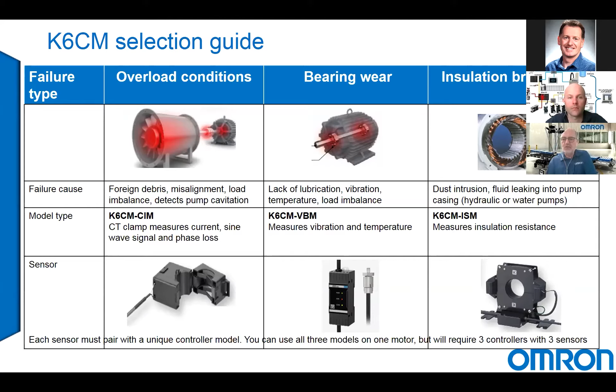The vibration one in the center will verify the wear and tear of your bearings in your motor, or if you use pillow blocks for a fan or something else, it can monitor vibration. It doesn't have to be the motor itself, but also the load of the motor that will be monitored with temperature and vibration. And the last one is insulation breakdown. If your motor has some water ingress and rust inside, there will be a breakdown of the coils inside, and the insulation current will be monitored with that third clamp here.